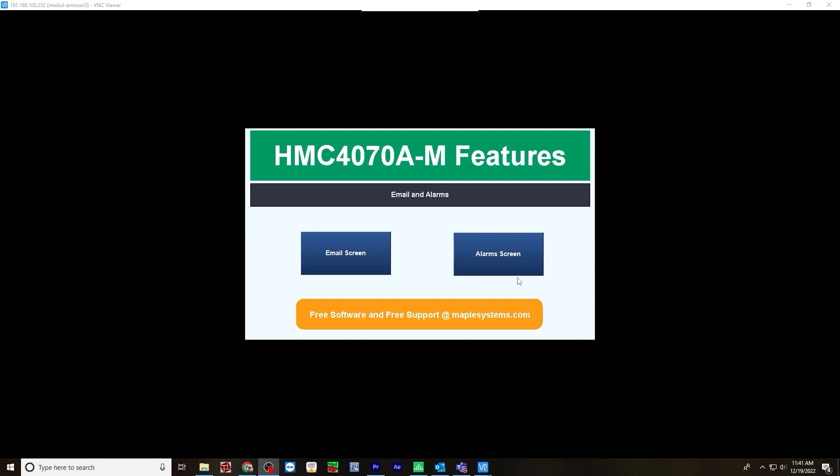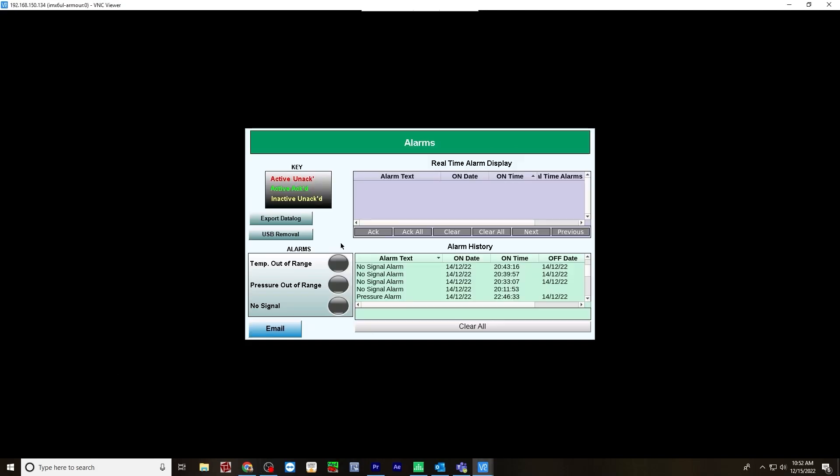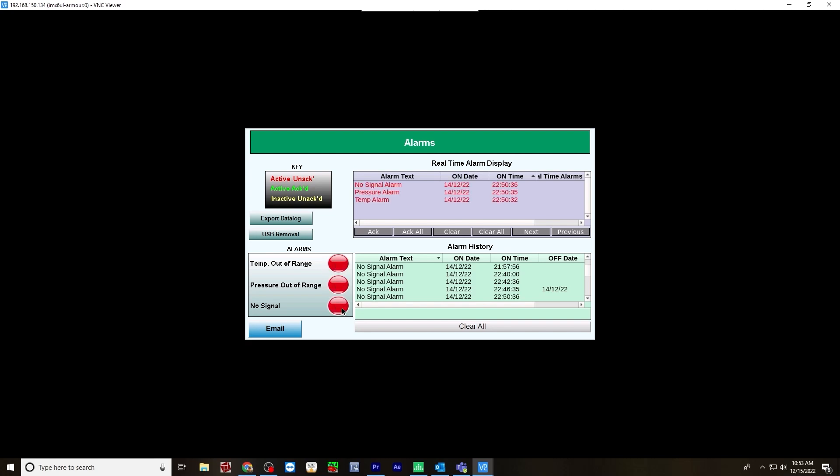So from here, let's click the alarm screen. I'm going to send out an email. And now when I trigger an alarm, it should send an email out automatically. And I'll show you that in a little bit. But let's trigger this alarm. Pressure out of range, no signal.